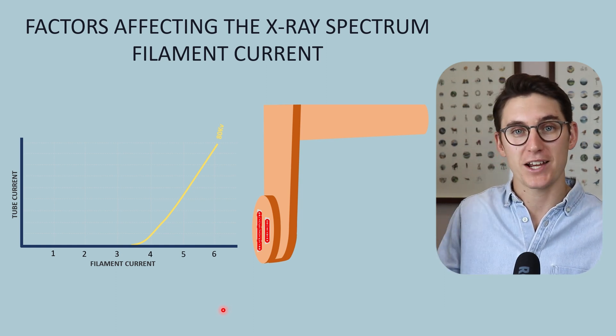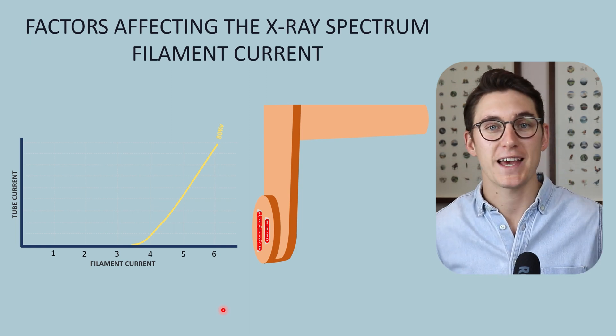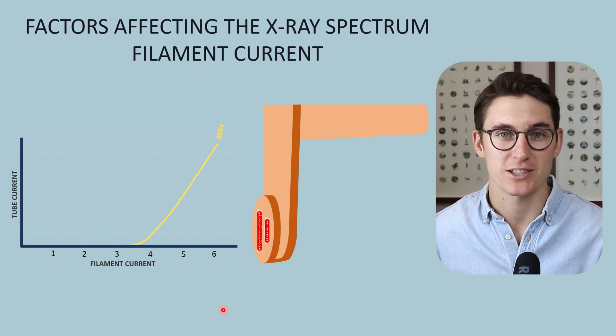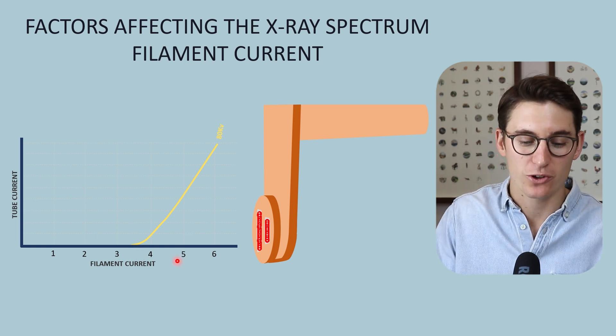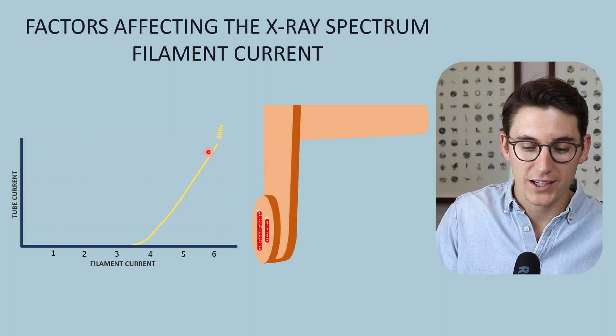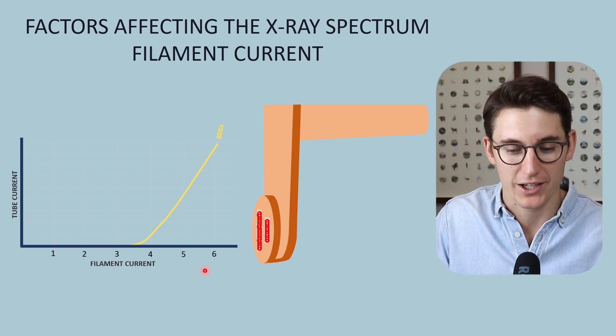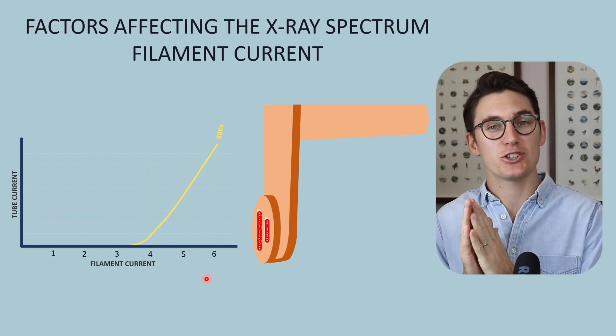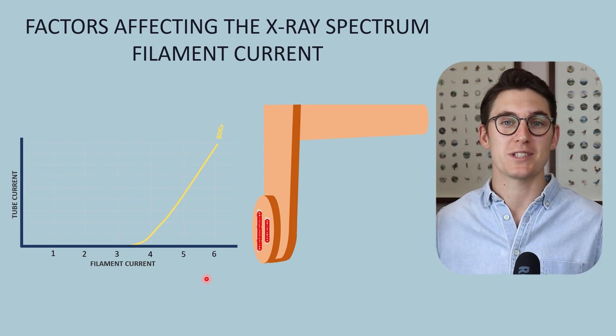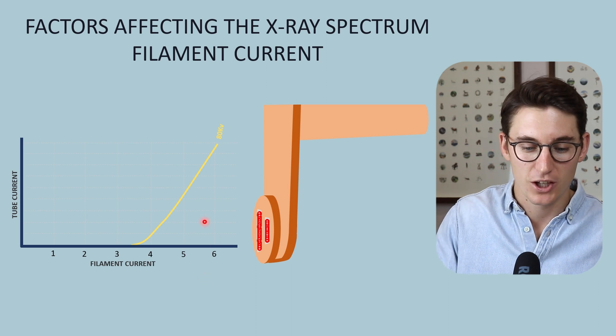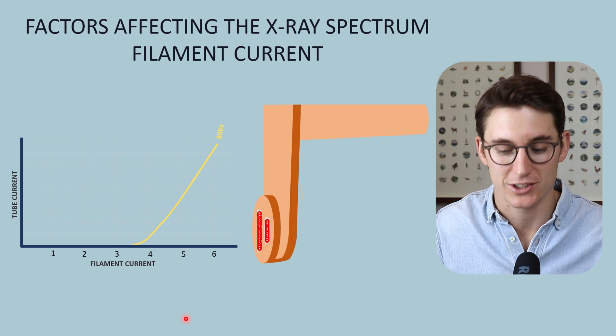Our tube current is the number of electrons flowing across our x-ray tube, and that is proportional to the number of x-rays we produce. So it logically makes sense that as we increase our filament current, we increase our x-ray number — the quantity of our x-ray beam. We are doing nothing to the energy of those x-rays; that is our tube potential that changes the energies. So our quantity increase is proportional to our filament current increase.